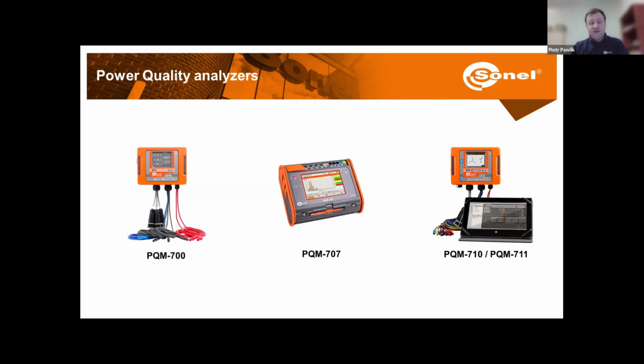It has an embedded large display, so here we can connect it and see live different graphs, different parameters, what's going on. It is also capable of recording over a period of time. However, the protection of the cover is better on PQM 700 or 710, 711. They have IP65 and PQM 707 has IP51 of the cover. So if you want to leave the meter outside and it may rain on it, there could be dust around, then PQM 700 or 710, 711 are just protected in a better way.